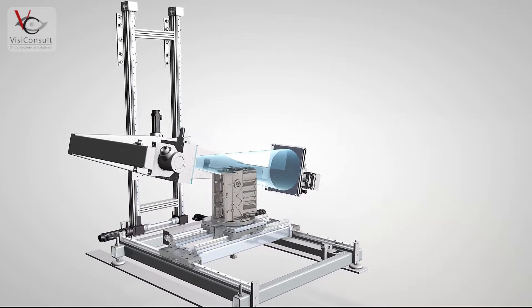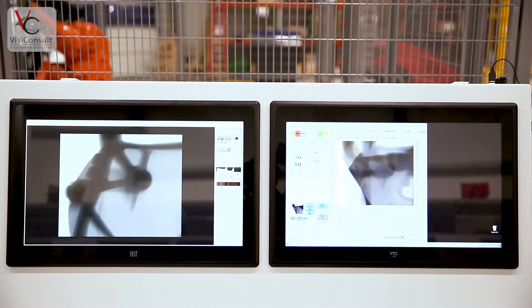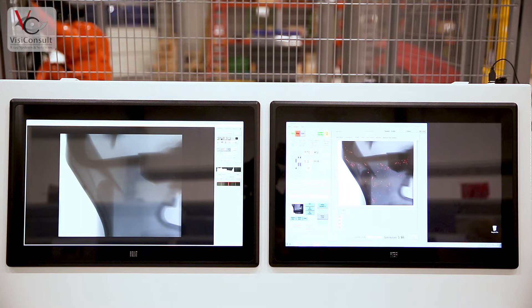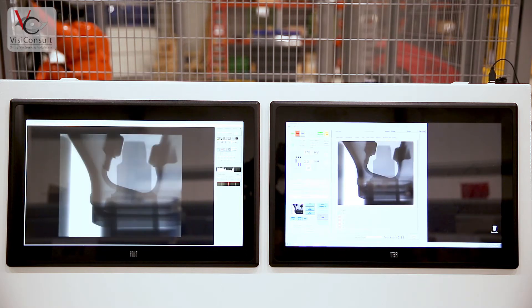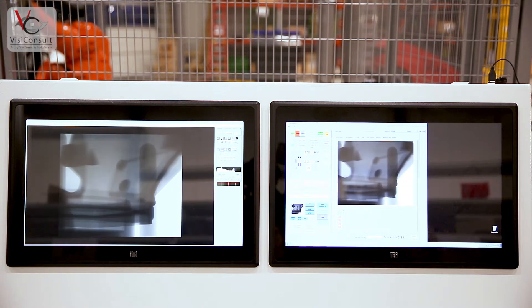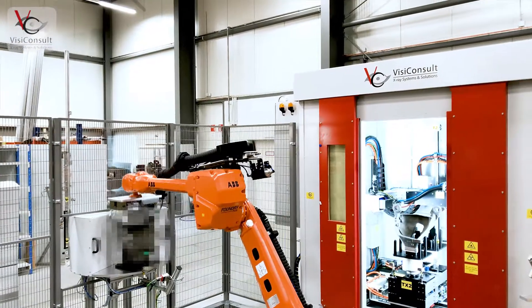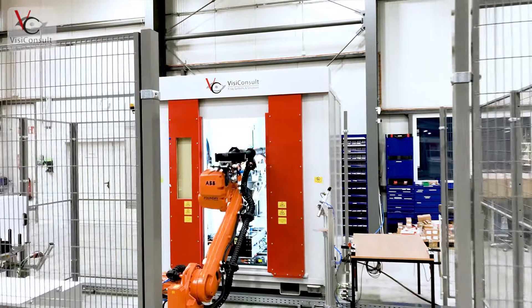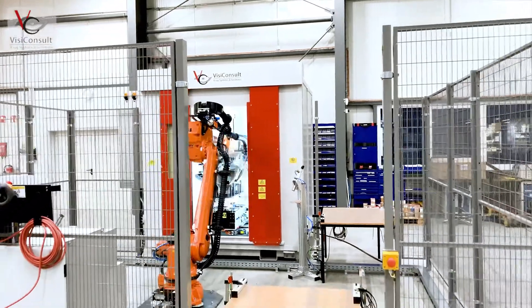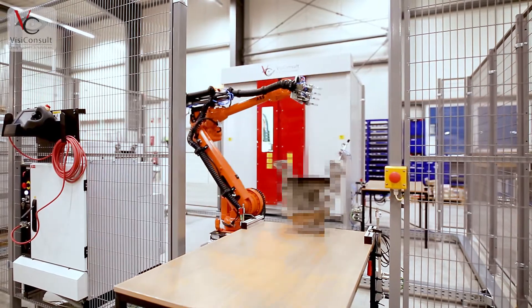These results can be automatically evaluated or stored for future inspection. The X-Plus ADR software is the most advanced automated defect recognition suite worldwide and allows inspection towards different metrics like porosities, inclusions, defects per area, dimensional measurements, completeness checks, and is approved by all major automotive OEMs.